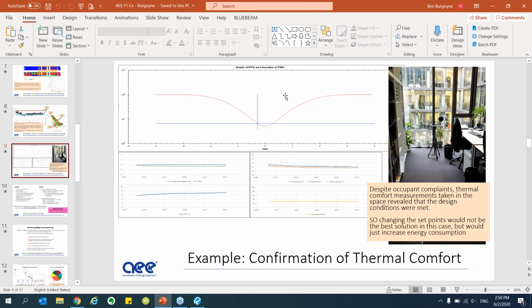These two acronyms come from ASHRAE Standard 55, which quantifies and details thermal comfort for people based on what their activity is in the space. Are they moving around? Is it a gym, or is it an office where they're just sitting there, with different metabolic outputs, and also breathing and sweating, mixed with the kind of clothes that they tend to wear? Again, in a gym, when they're wearing shorts and a t-shirt versus a full suit, and the time of year.